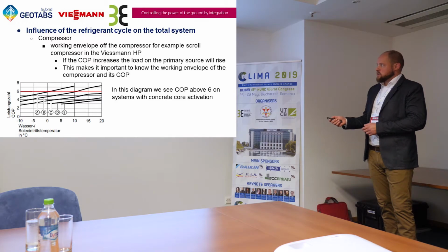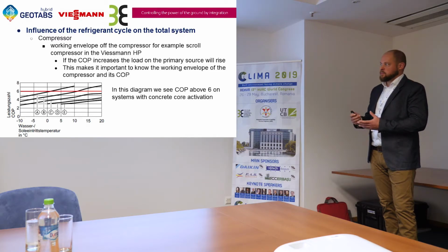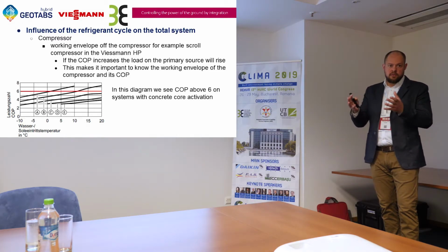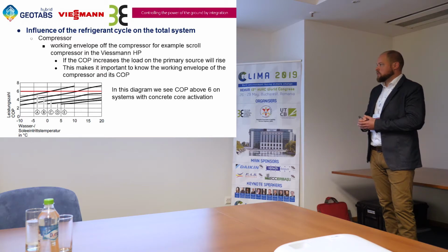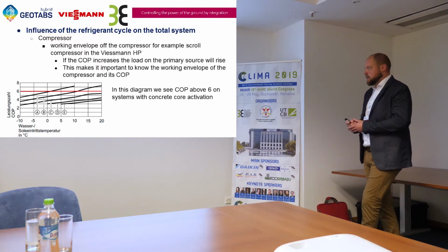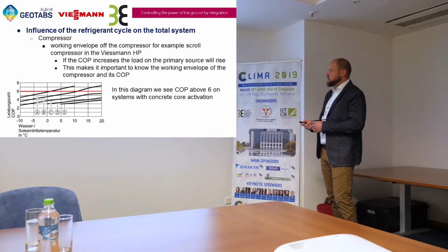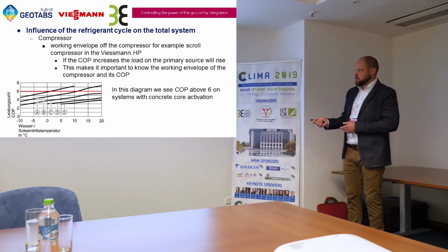So what's the influence on the source? If the COP increases, the load on the primary source will also increase. This makes it important to know the working envelope yet again, because we have to know the COP of the system, and then we can effectively calculate the load on the source.